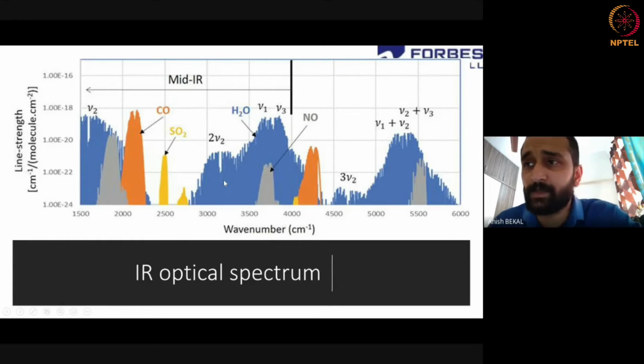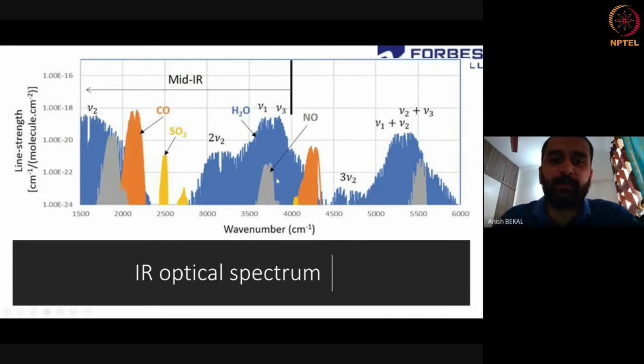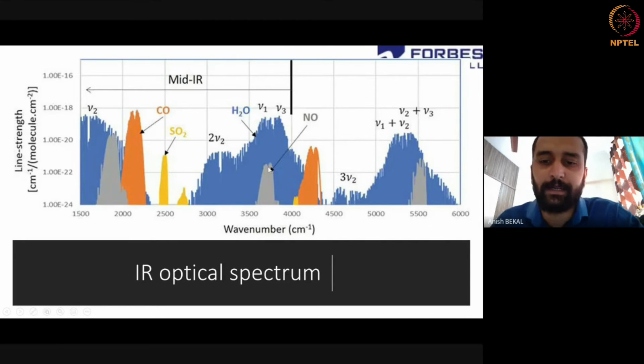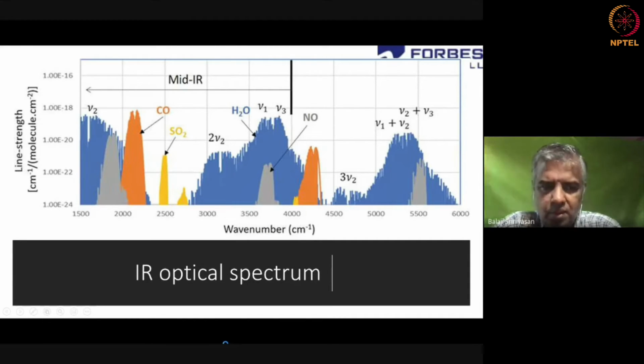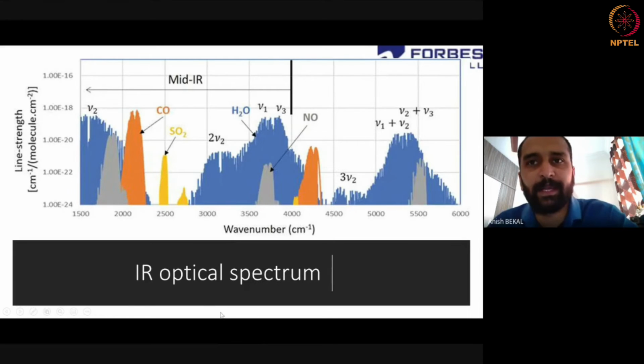You cannot make a sensor with 1 ppm sensitivity by looking at the entire spectrum. However, techniques like IR optical spectra depend on a lamp and broadband excitation, so they can't achieve very high sensitivity in the presence of interference. But if you look deep into the cluster of spectrum, there will be one or two lines where interference is minimum. A tunable diode laser can go directly to that region. The problem then becomes getting a tunable laser of that particular wavelength. For a long time there were no lasers operating in the mid-IR region, but now they are available.